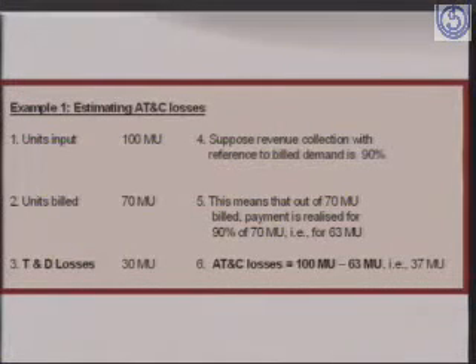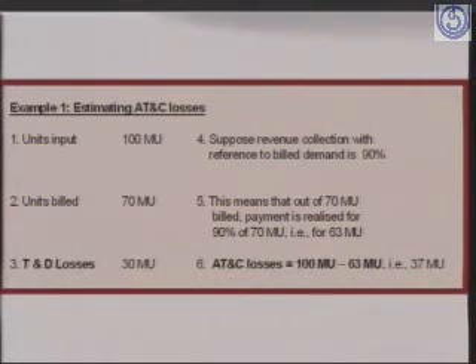As an example, well explained in your book: suppose units input is 100 million units, and units billed are 70 million units, meaning bills were generated for that amount. So T&D loss is 30 million units in this case. Suppose revenue collected with reference to billed demand is 90%, meaning revenue collection is only 90% of the 70 million units - then the utility collects revenue for only 63 million units. So T&D loss is 30 million units, but AT&C loss amounts to 37 million units. AT&C losses will always be higher than T&D losses.